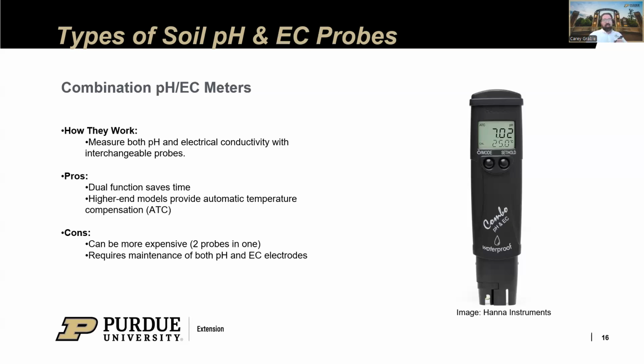A lot of times I keep saying you've got to keep that probe moist. There's a cap on here that comes off, and I just keep a piece of sponge down in there that I keep moist - that's enough. It doesn't have to be wet, it just has to have a moist environment. So the maintenance side isn't terrible, but it is a consideration you have to think about.